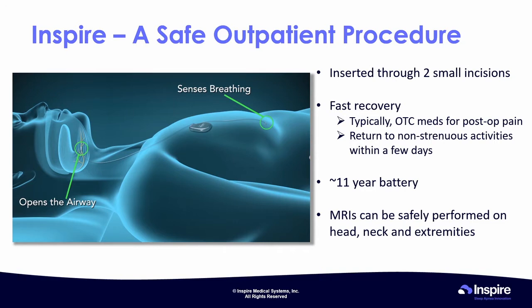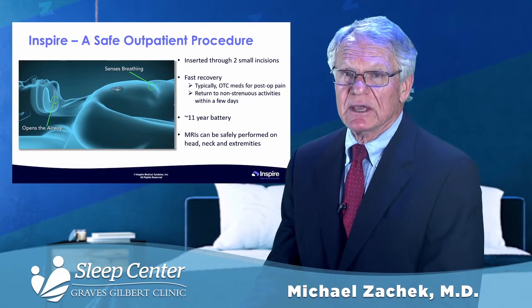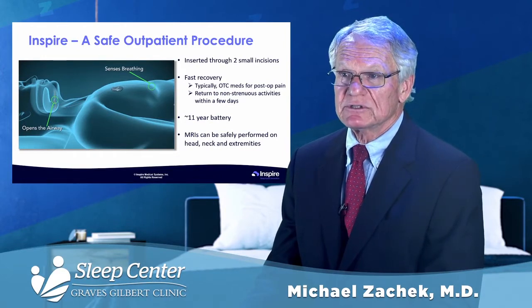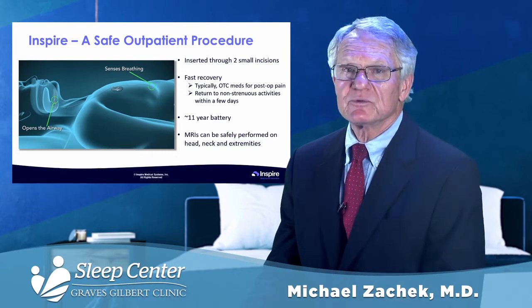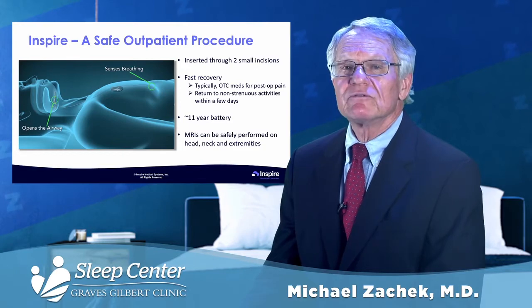Questions come up about how long does the battery last. In general, it's programmed to last about 11 years. And people often ask, can I have an MRI with this device? Well, MRIs, of course, are magnetic devices, and we can do MRIs of the brain, we can do MRIs of the extremities, and do those safely. Probably can't do them to the thorax because the device would be implanted. Sort of the same as a cardiac pacemaker. So a pretty simple device.